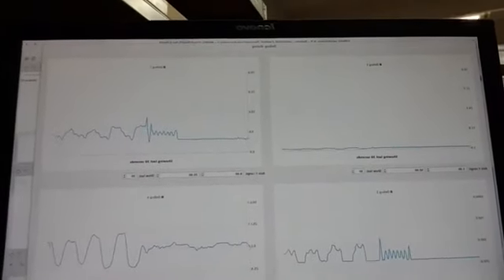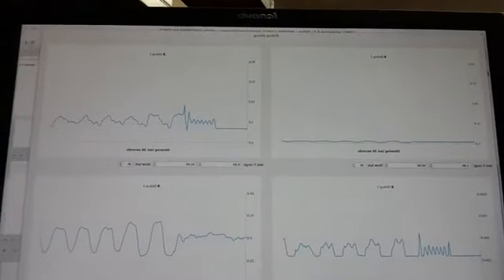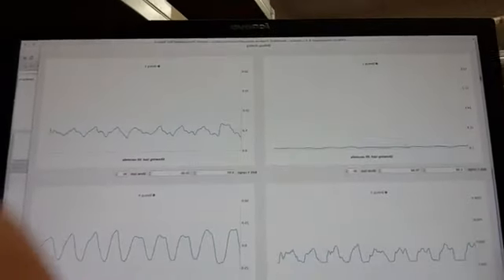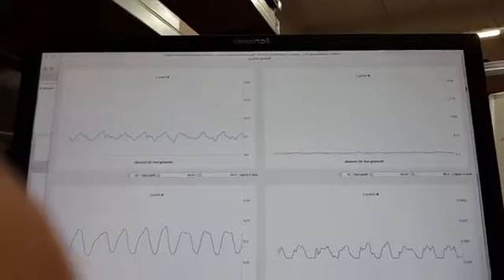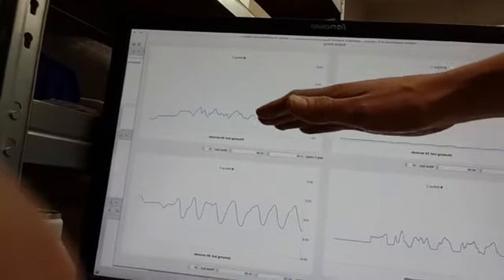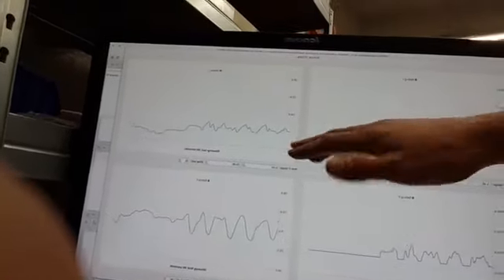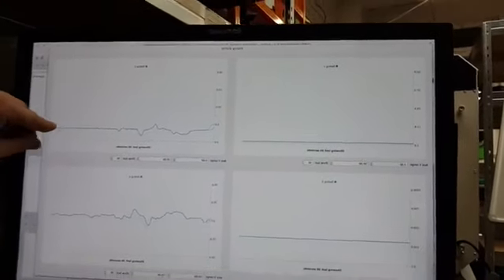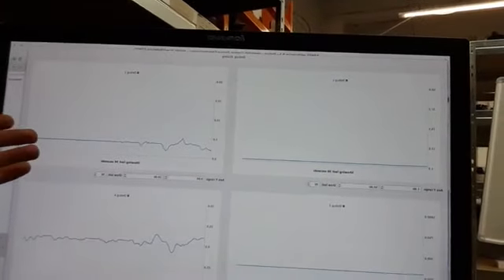I'll turn the machine from idle mode to real mode — it will be slightly louder so I'll speak louder. At the switching time you see some noise, but now we're having very little variance. You want to avoid the pressure getting too low — getting a little too high is not so harmful, but getting too low is very harmful for your patient. The graph shows the pressure the patient is breathing, measured in centimeters of water.